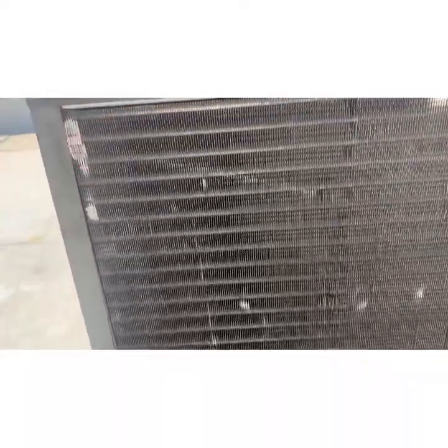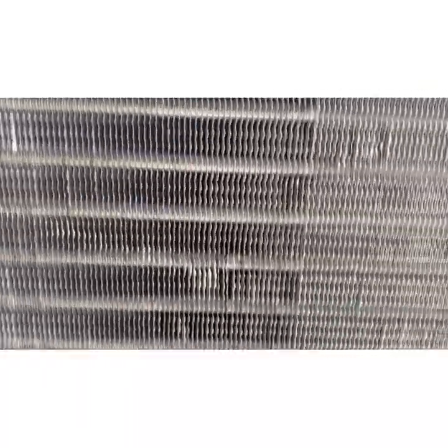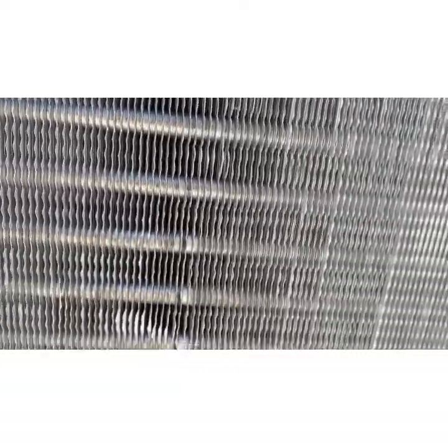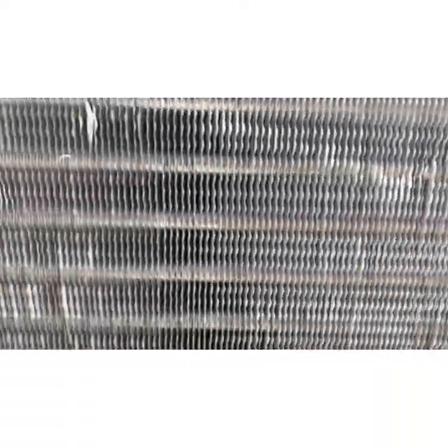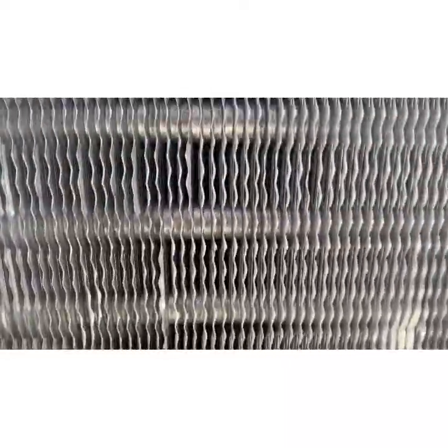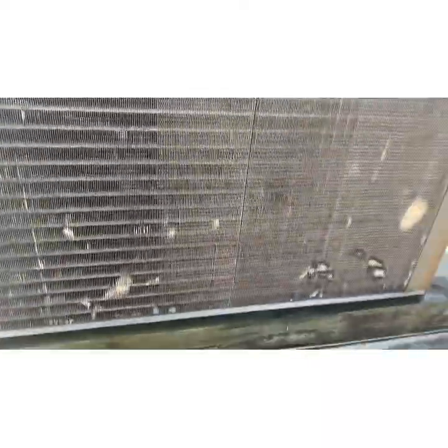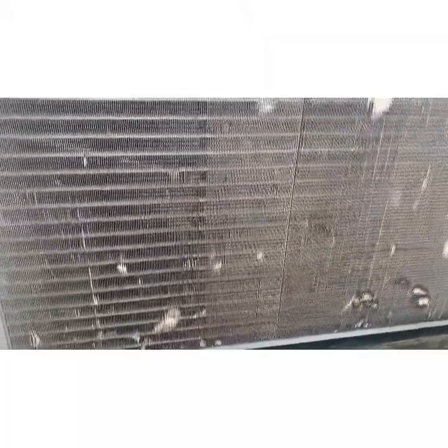The coils right off the bat, looking at them, are pretty gross and greasy. It's not like it's plugged up solid, but as you look at it, this is a restaurant that does hamburgers. So they put out a very special kind of grease. That definitely manifests itself on equipment nearby. So let me get out the coil cleaning supplies and we'll get started.